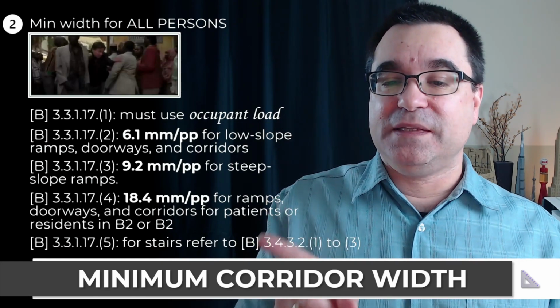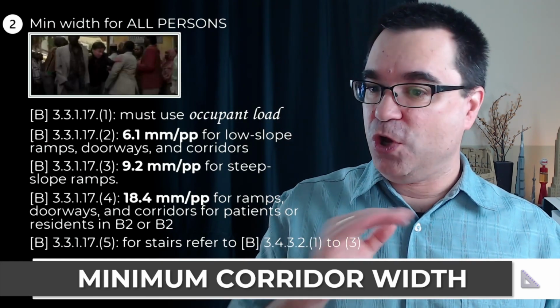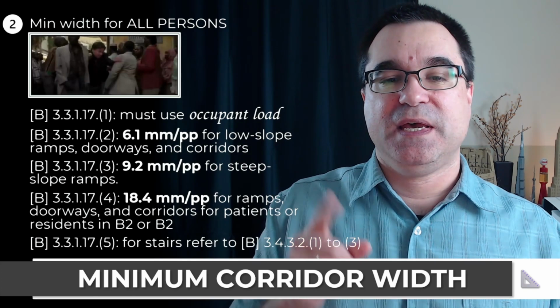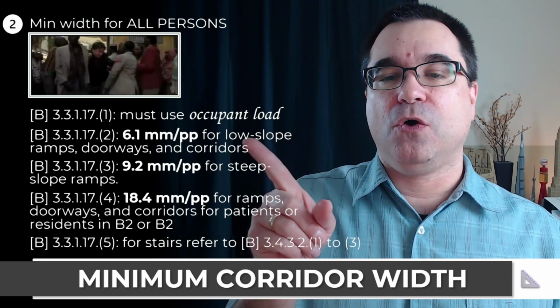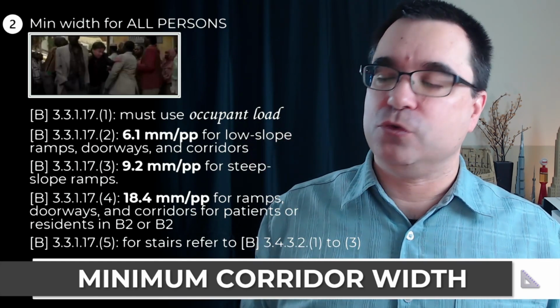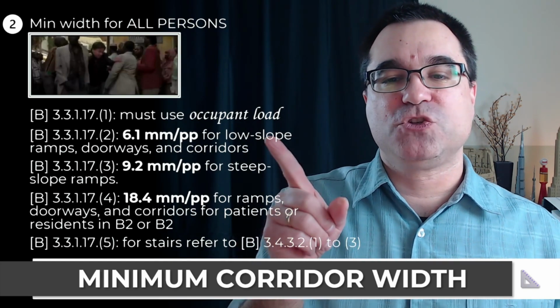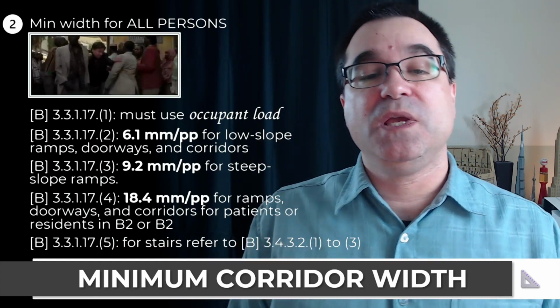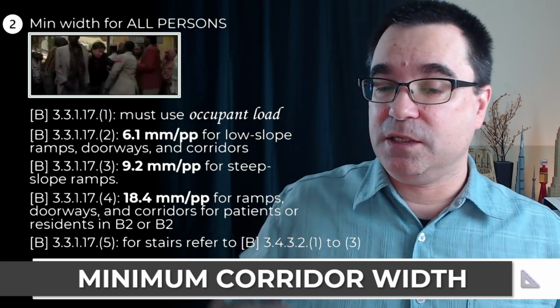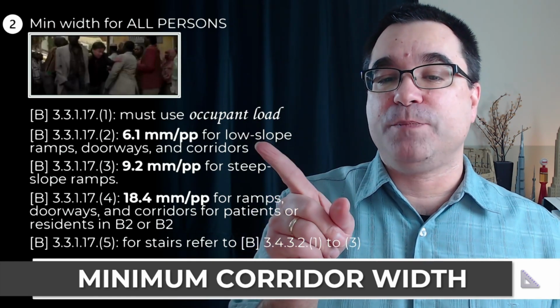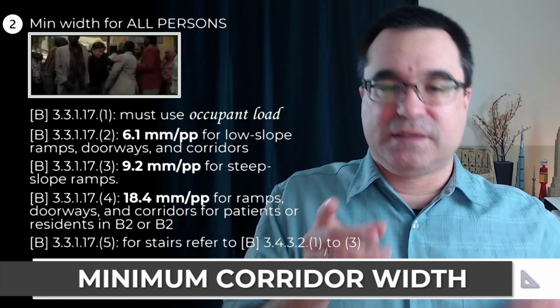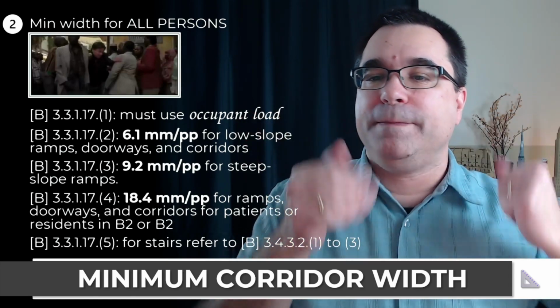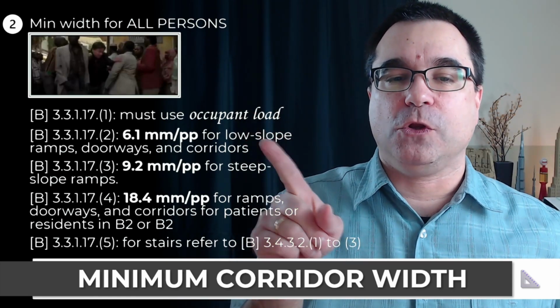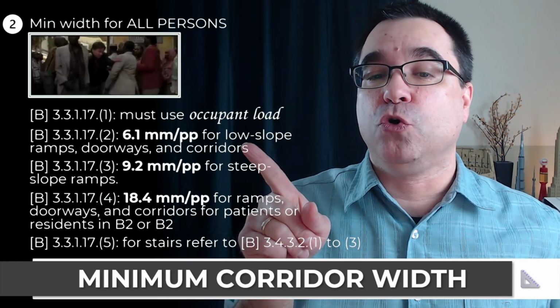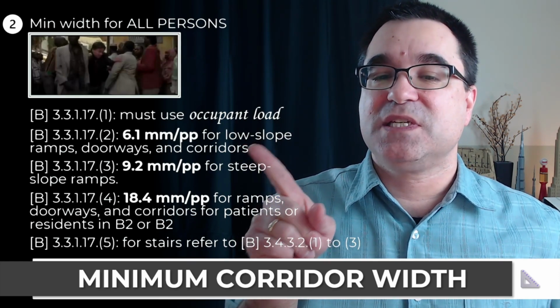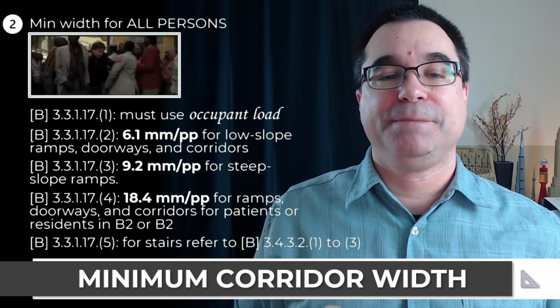And what the building code says for non-exit related dimensions is that depending on what you're looking at, you have to use the correct sentence. So under sentence 3.3.1.17.2, for every person, you have to give that specific item 6.1 millimeters of width. And that's for low slope ramps, doorways, and corridors, 6.1 millimeters per person.